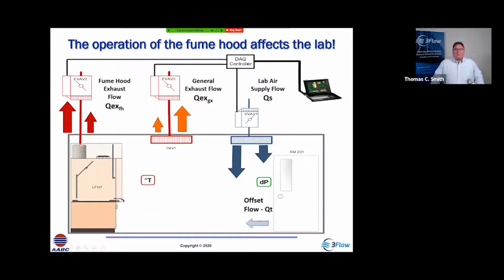So now we use this information from the fume hood. If we've tuned this properly and we've got proper response through the hood, it's connected to the controller that's controlling supply. So as I mentioned, if it doesn't set up properly, if it's not properly configured, that's going to cause air balance problems and other control issues, possibly with temperature control within that space. So the hood can drive the flow for a space, and we need to make sure that it is accurate and precise when we're doing our measurements so that we've tuned it properly to function over the range of operating modes. And so we have to look at this holistic system in order to achieve the objectives of safe, energy efficient, and productive spaces.